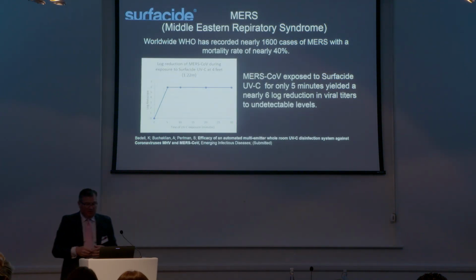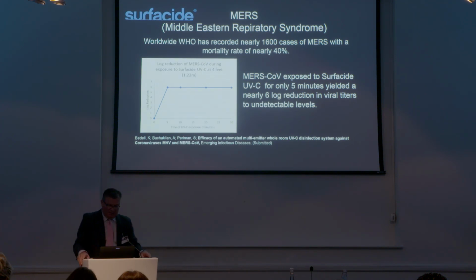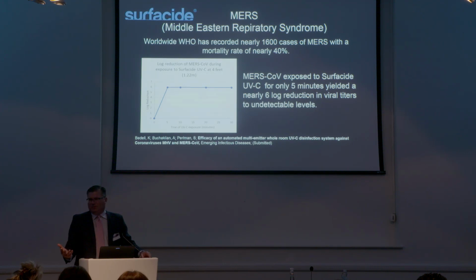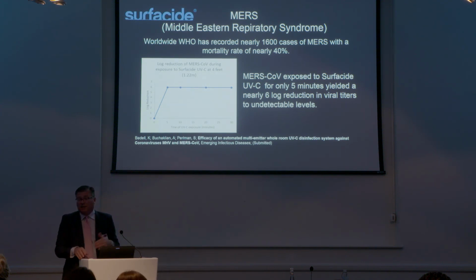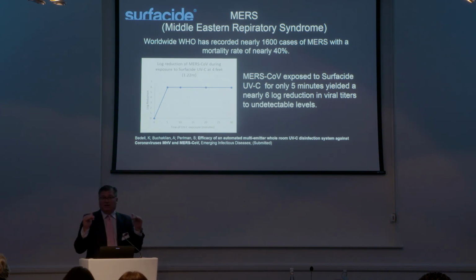And this study proves this. This was done at the University of Iowa, but in a 5-minute cycle, we yielded a 6-log reduction in the MERS virus. It's just very susceptible. 6-log translates to virtual sterility. The FDA in America equates 6-log to sterile or high-level disinfection. So an incredibly high effective kill at a low dose for just 5 minutes.